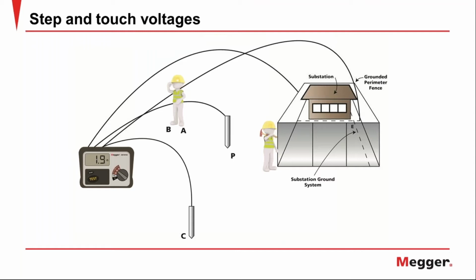So speaking of personnel, here's a most fundamental test. Now, this is done primarily at substations, but if you're in a big industrial facility, maybe with on-site generation or something like that, this could also be relevant, possibly. This is step and touch potentials. And what these are, it's a way of measuring the maximum voltage a human could be subject to in the event that a fault clearance is in progress.